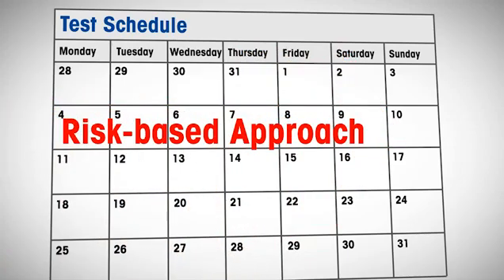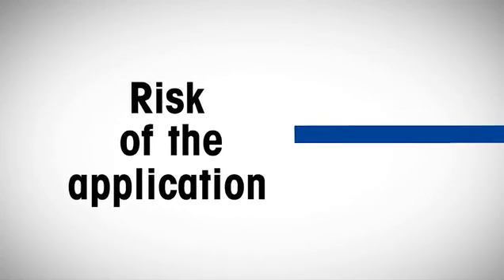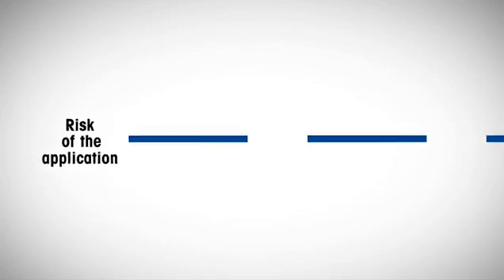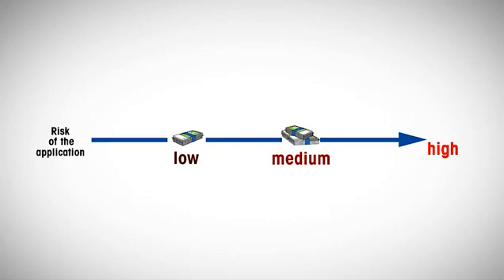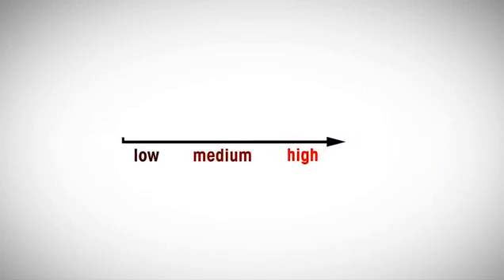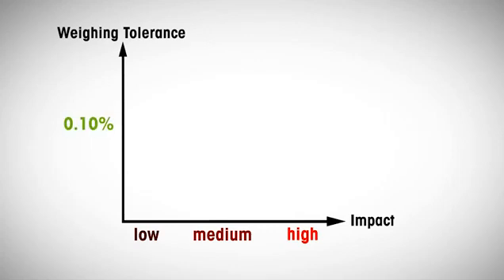Two factors influence the test frequencies. First, the risk of the application. For example, let's classify the impact of potentially inaccurate weighing results into low, medium and high. With low having none or little consequences on product quality or costs, and high meaning that a drug could be ineffective or toxic.